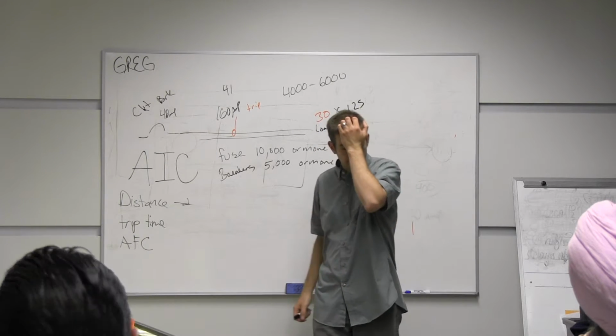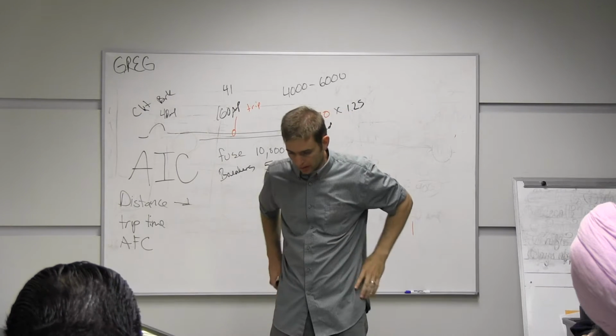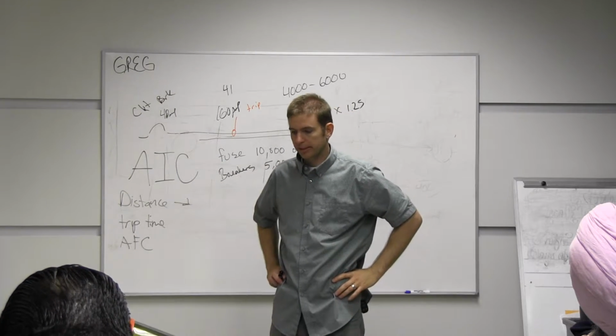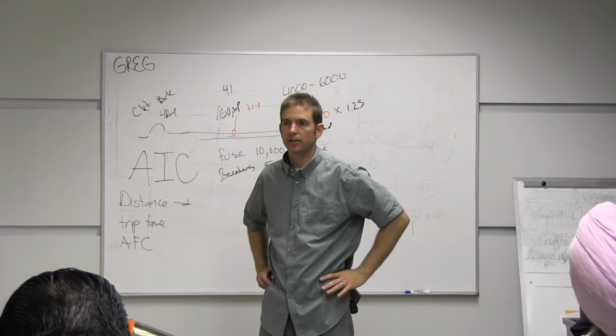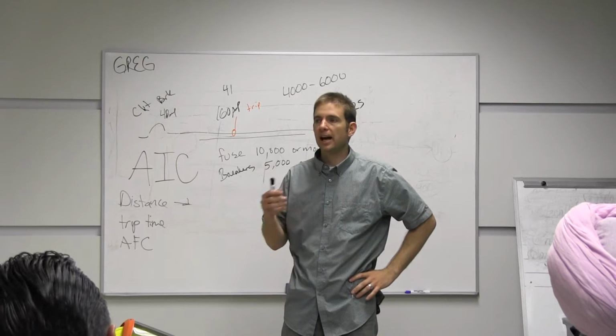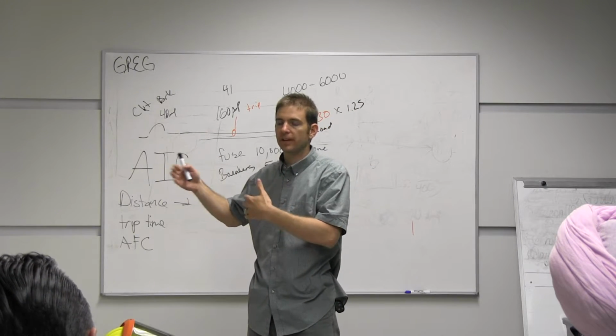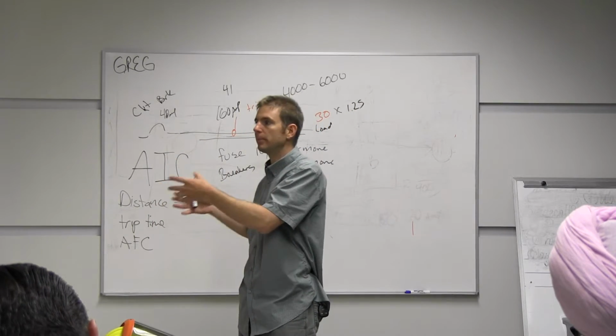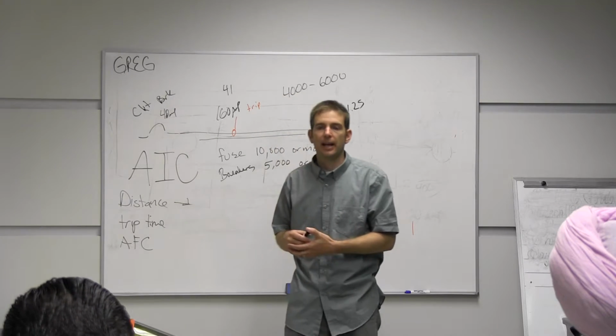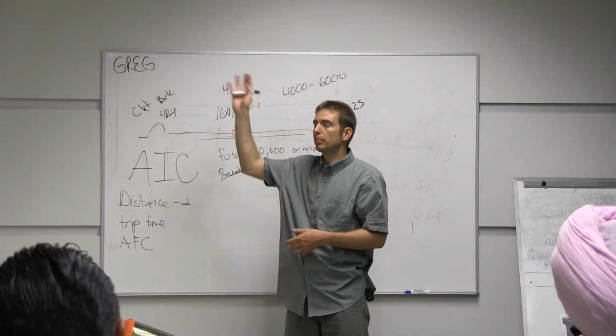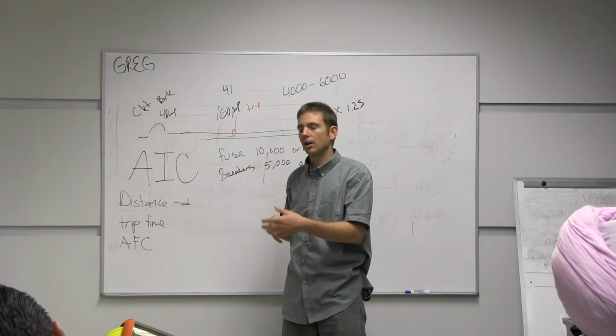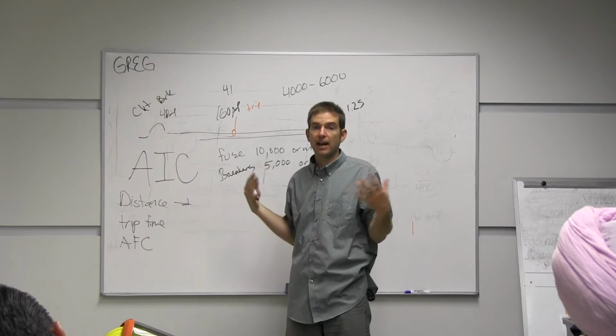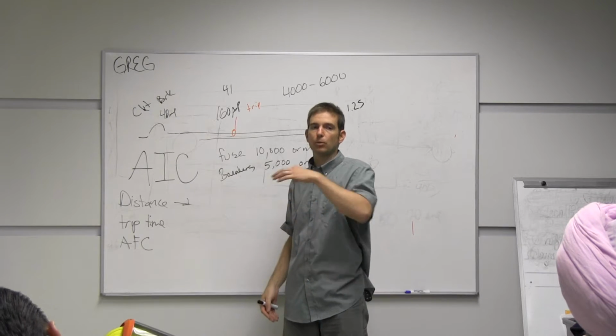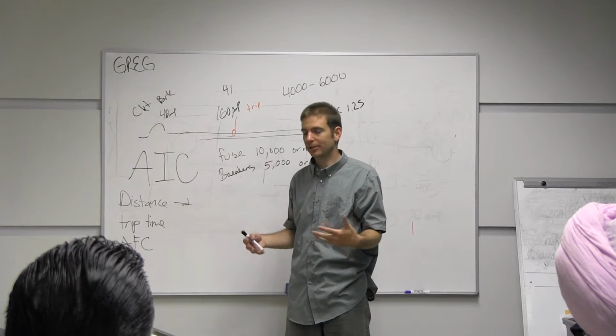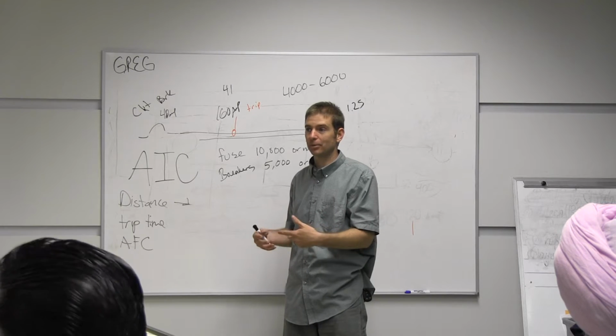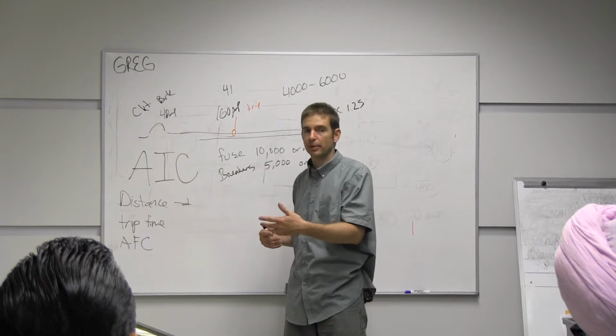When I was at another tunnel, they have a different problem than you guys have. They have a facility that's about 70 years old. And over time, electricians and people were making changes, fixing things, installing pieces of equipment, removing pieces of equipment, repairing damage. And let's say we re-pull all these conductors and we had 10 conductors in a wire. Well, you know what, I don't need that one, I don't need this one. And all I have is black, so we're just going to pull 12 black wires through this raceway. Now I've got 12 black wires, I don't know which one's which. Nobody does, they're not labeled, they're all black. And some are spare, some are not spare, some went away.